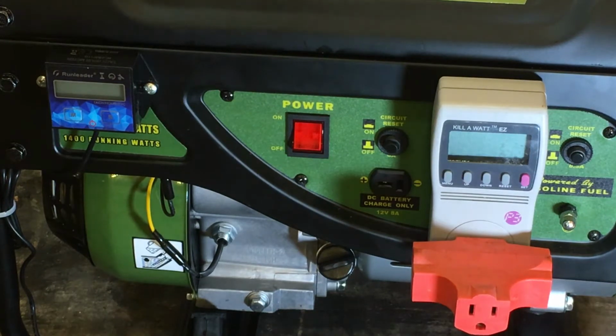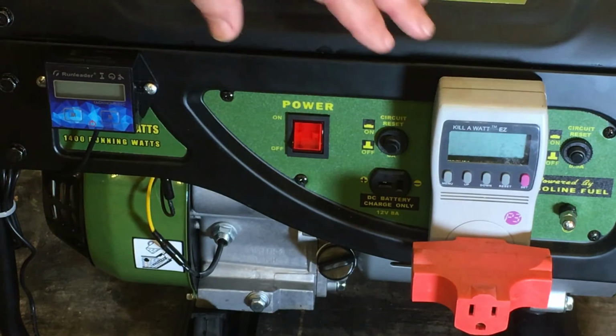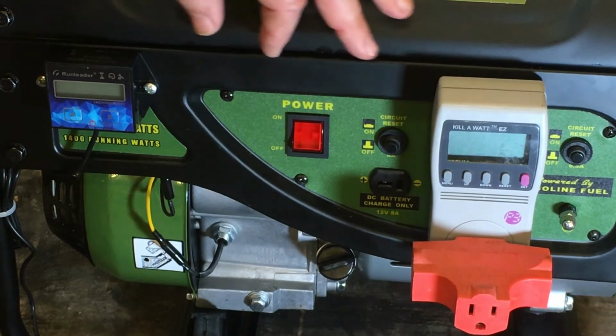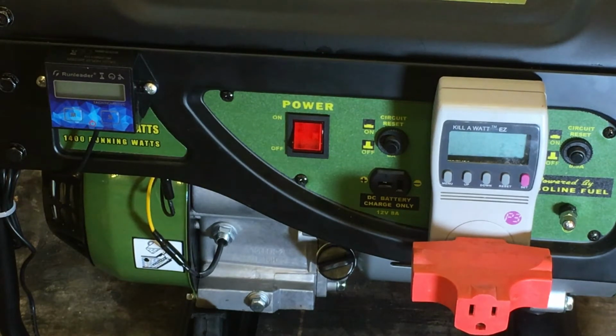So then I went ahead and pulled to the high heat, which should bring the unit up to the full 1400 watts. The engine did carry the load - it continued to run - but the output voltage, as recorded by this device, was down to 101 volts, and the frequency was at 55.7 hertz.